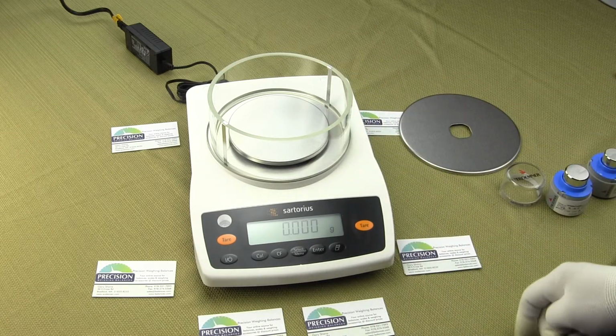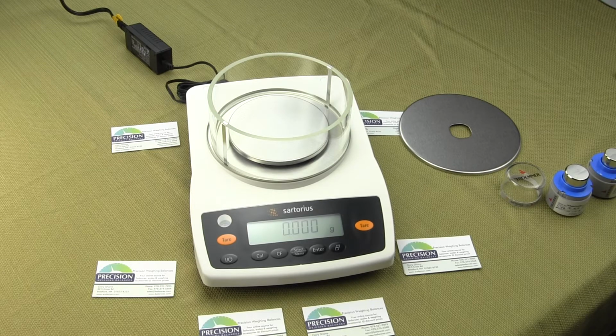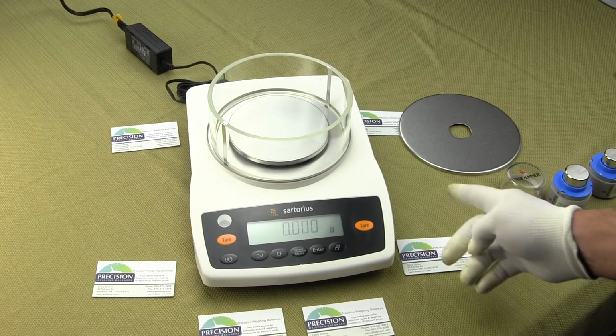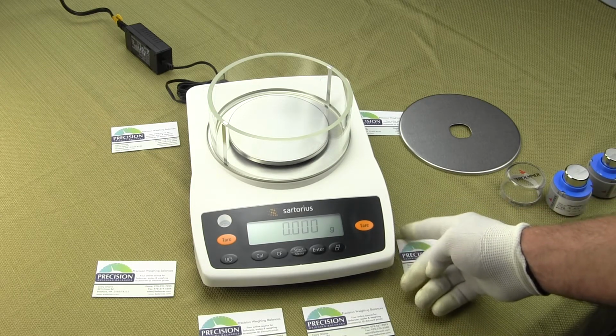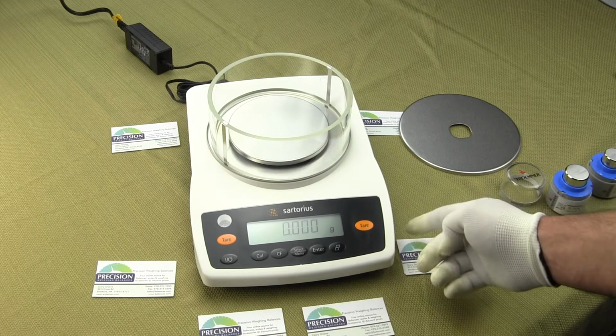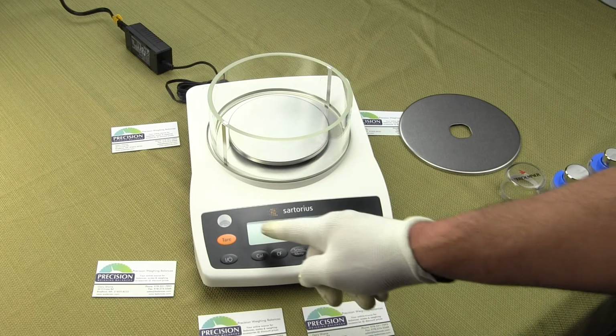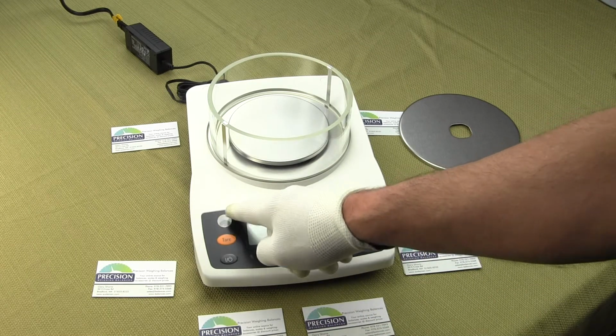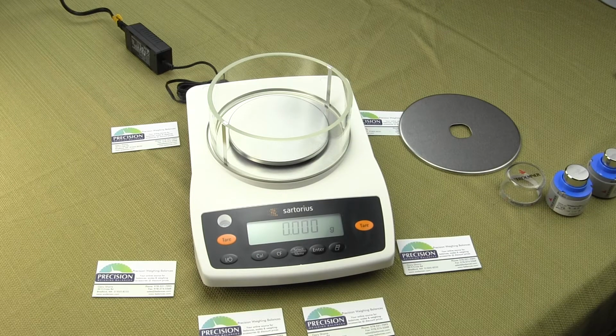So, to perform calibration is real simple. All one needs to do is you'd want to level your balance, and after I do the calibration, I'll turn the balance over to show you. But we have two leveling feet in the front, and we do have a spirit bubble in the upper left-hand corner. This area here, this is where the spirit bubble is. And you want to make sure your balance is level before doing calibration. You also want to make sure your balance has been running for at least a half hour. We've had this balance running for an hour.